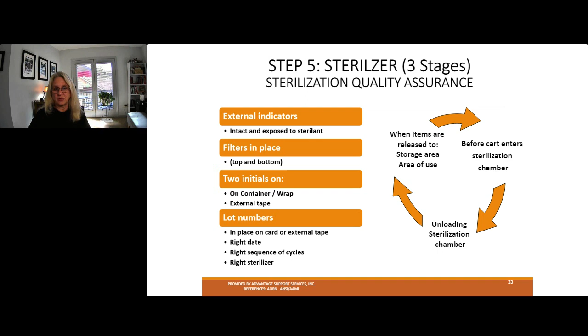The sterilizer cart unloading and inspection after unloading. These are some tools that you can use and post before and after the instruments are loaded into a chamber. Loading the sterilizer with an inspection, a second inspection look. When I first started in sterile processing, I would use the gun to help sticker all the loads. And I swanny every time that gun was left on the sterilizer cart, and I melted that thing every time until I figured out I have to remove this. I needed a little reminder to remove the gun and not place it on the load cart before it goes into a steam sterilizer.